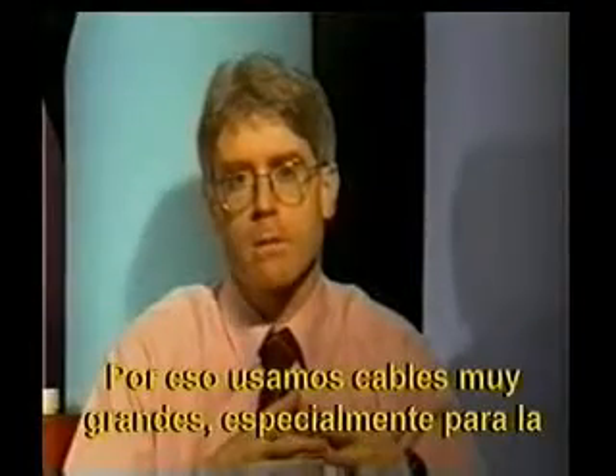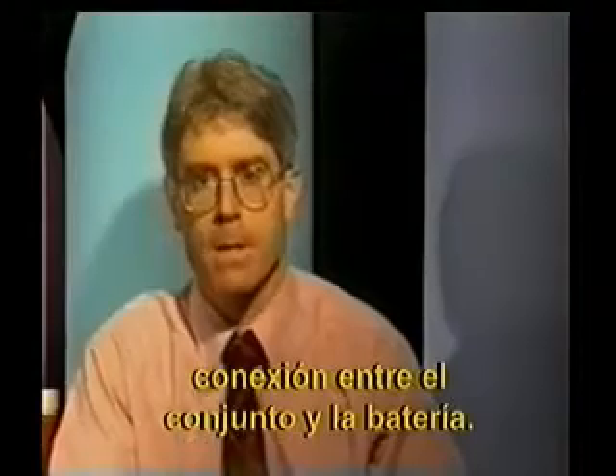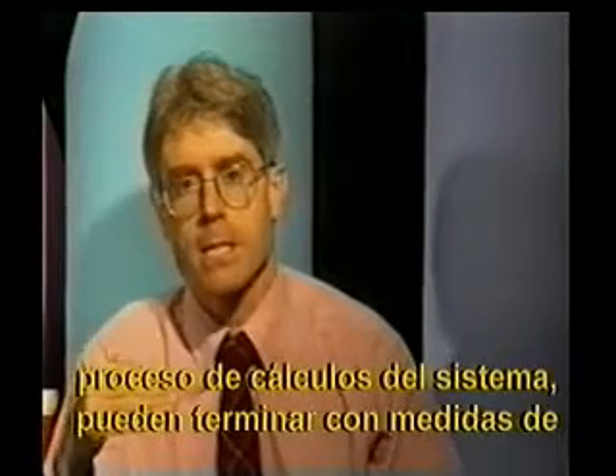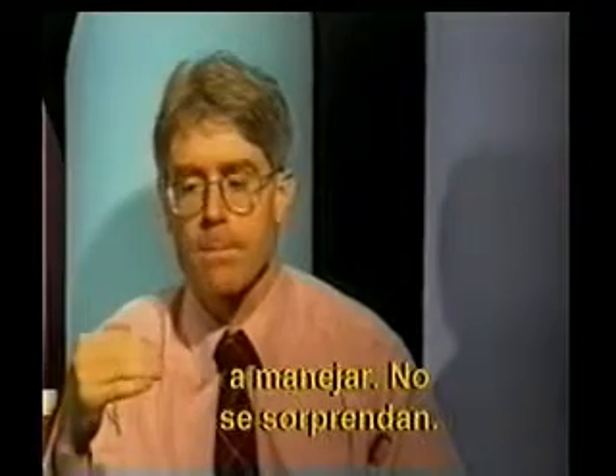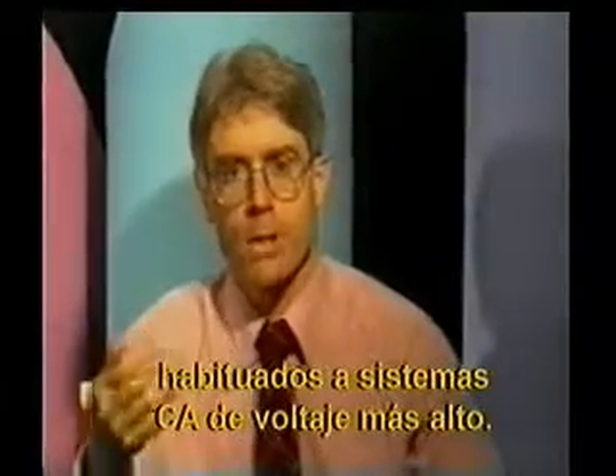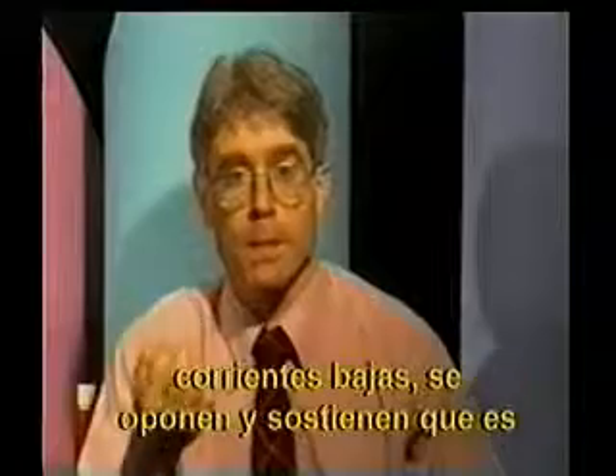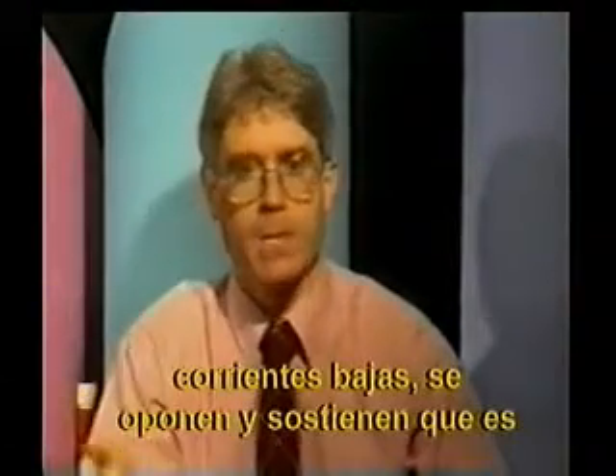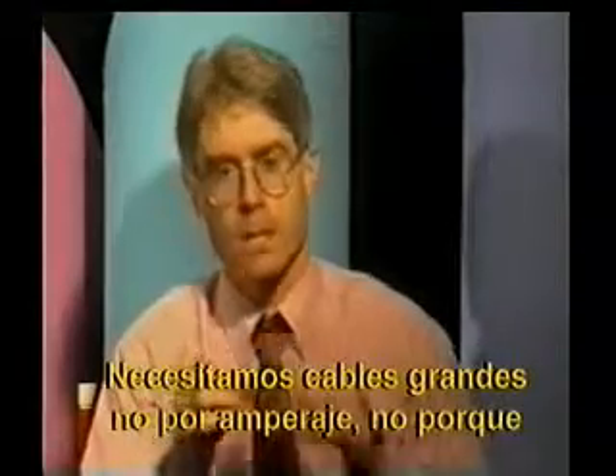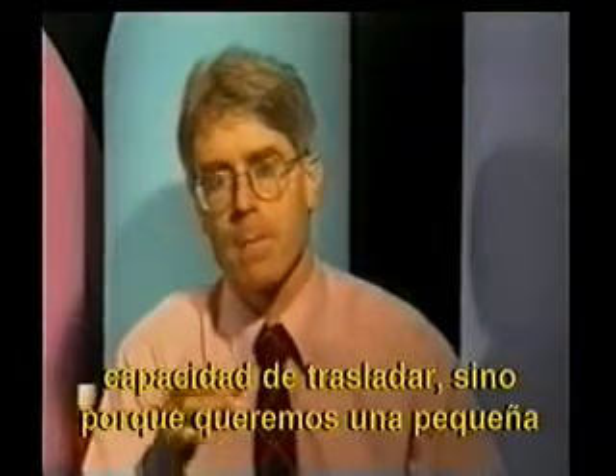We end up using, often, unusually large wires for the connection, especially between the array and the battery. I want to alert you to that fact because when we go through the process of our system calculations, you may end up with wire sizes that are larger than you're used to expecting. Don't be surprised. In fact, we often encounter resistance by electricians or engineers that are used to dealing with higher voltage AC systems when we propose using large gauge wire for relatively low currents. They go, why? This is wrong. You've made a mistake. We don't need that size wire. And they're wrong. We need larger size wires, not because of ampacity, not because we're carrying the current that that large wire could carry, but because we want the small voltage drop over a long distance that that wire gives to us.